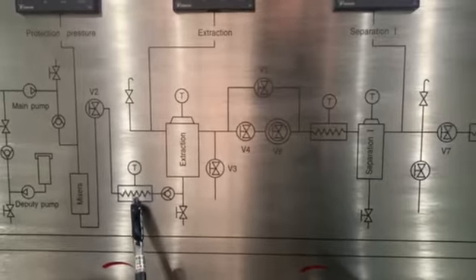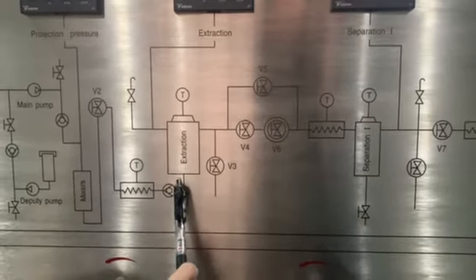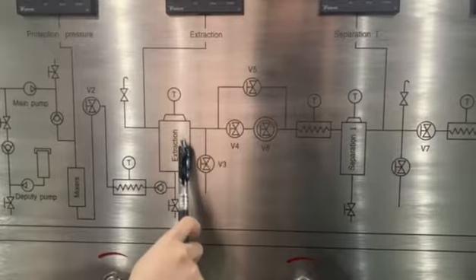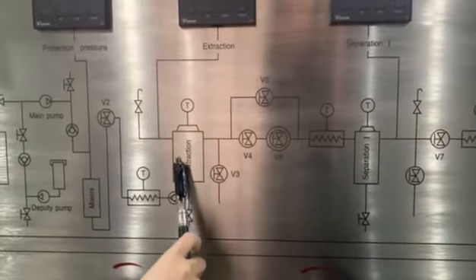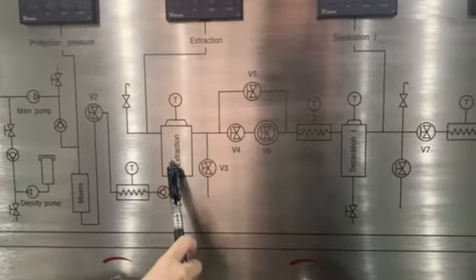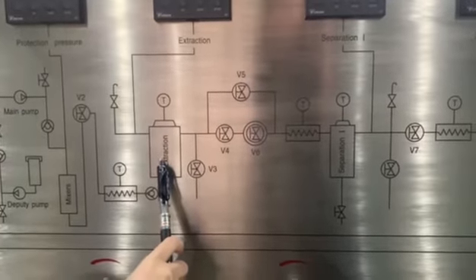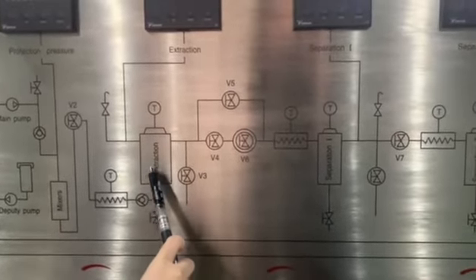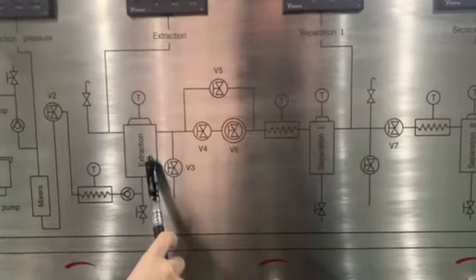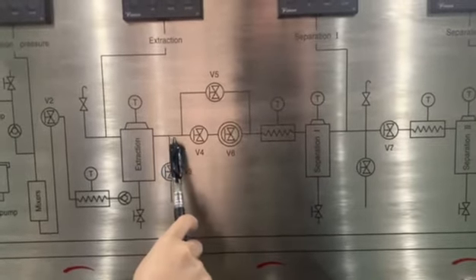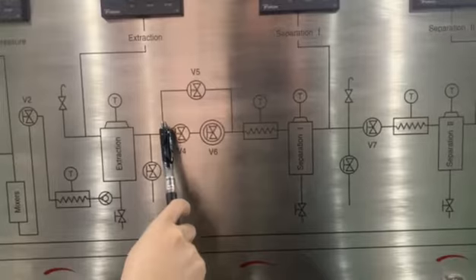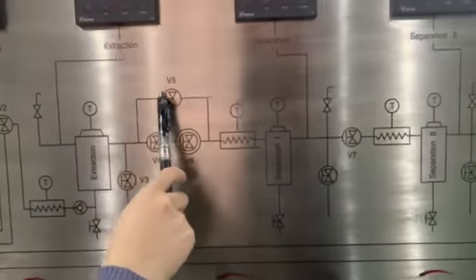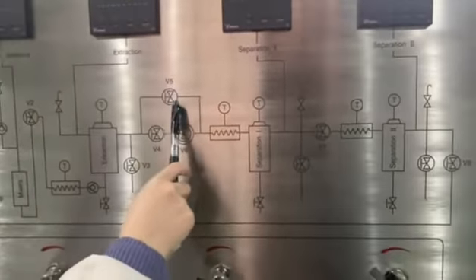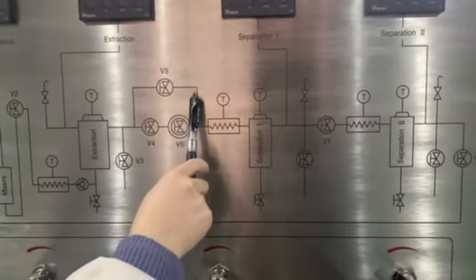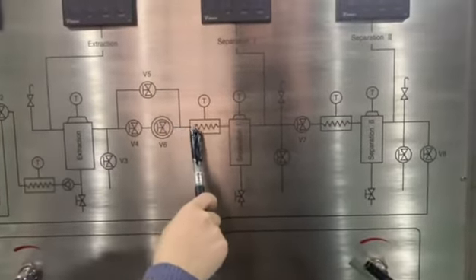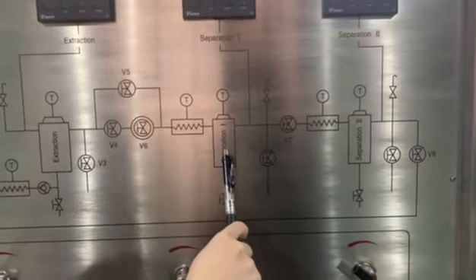The supercritical CO2 enters the bottom of the extraction kettle and fills the contents with the dry hemp or cannabis, then is extracted in the extraction kettle. The extracted CBD mixture and the CO2 from the top outlet of the extraction kettle pass through the high pressure control valve at the outlet of the extraction kettle and enter the first separation kettle for analysis.